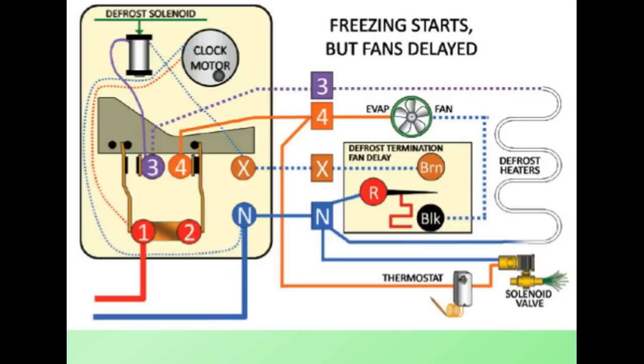Okay, so we have now terminated the defrost cycle. The freezing of the coil starts. We have power to the solenoid valve but the fan is delayed. Remember we looked at defrost termination and fan delay - there's a dead band between 25 degrees and the 55 degree contact.